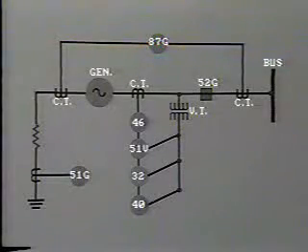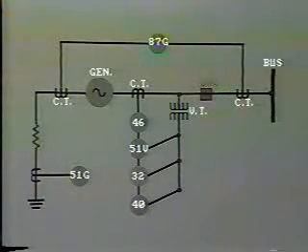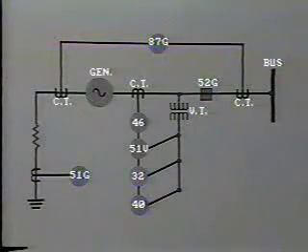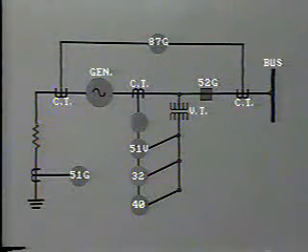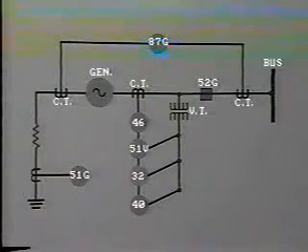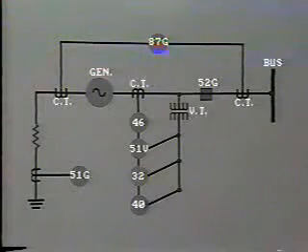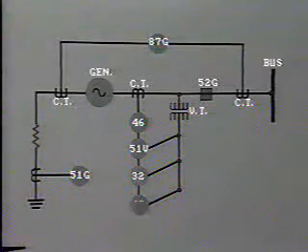Here is another simple protection diagram: a generator connected directly to a bus through circuit breaker 52G. You can already recognize some of these device numbers. 51G is a time overcurrent relay in the neutral to ground. 87G is a differential relay across the generator. Device 46 is a negative phase sequence relay. 51V is a voltage restrained time overcurrent relay fed by the CT in the generator output, and a voltage transformer which also feeds a directional power relay, 32, and a loss of field relay, 40.